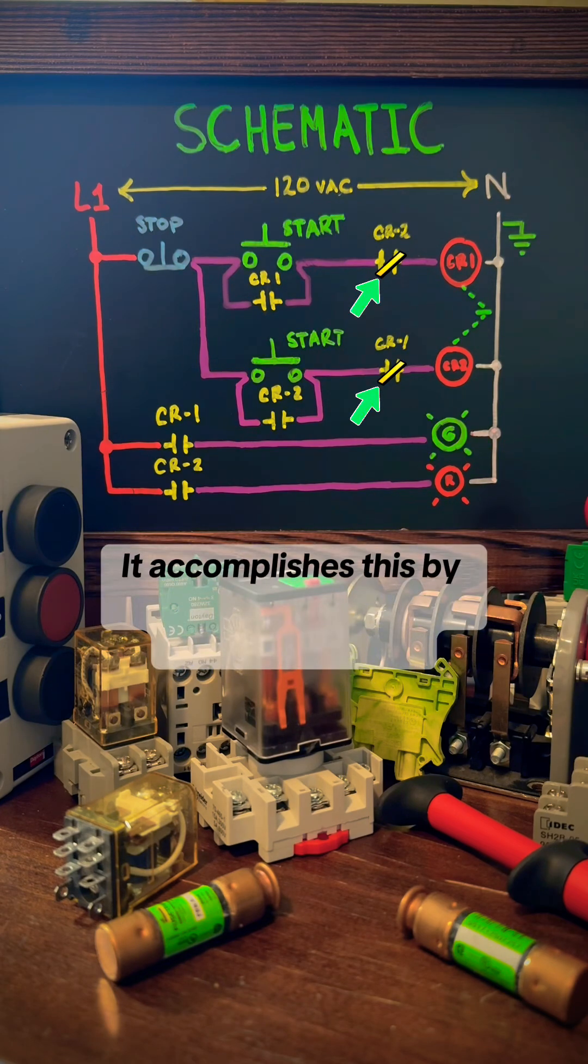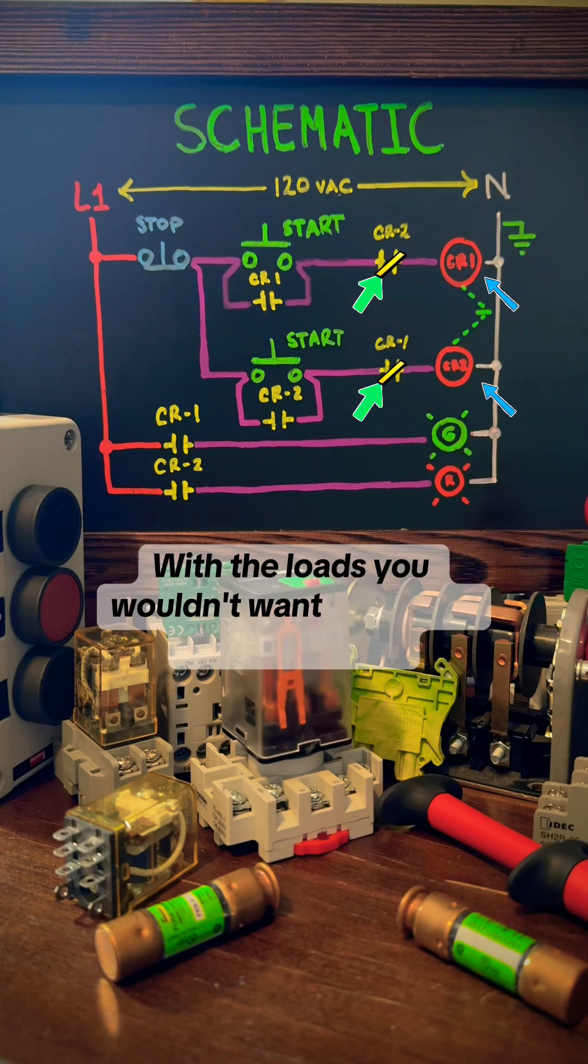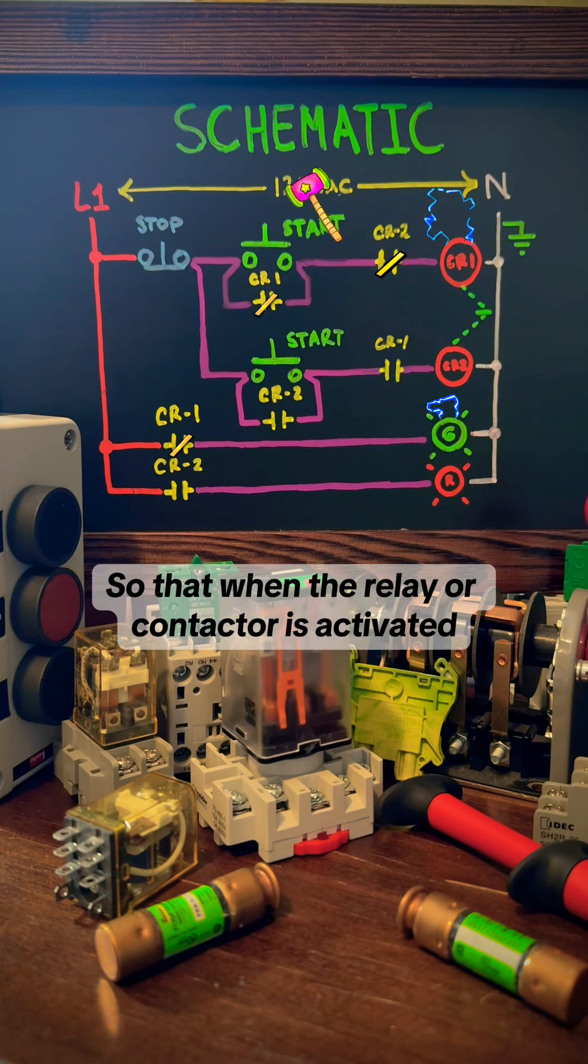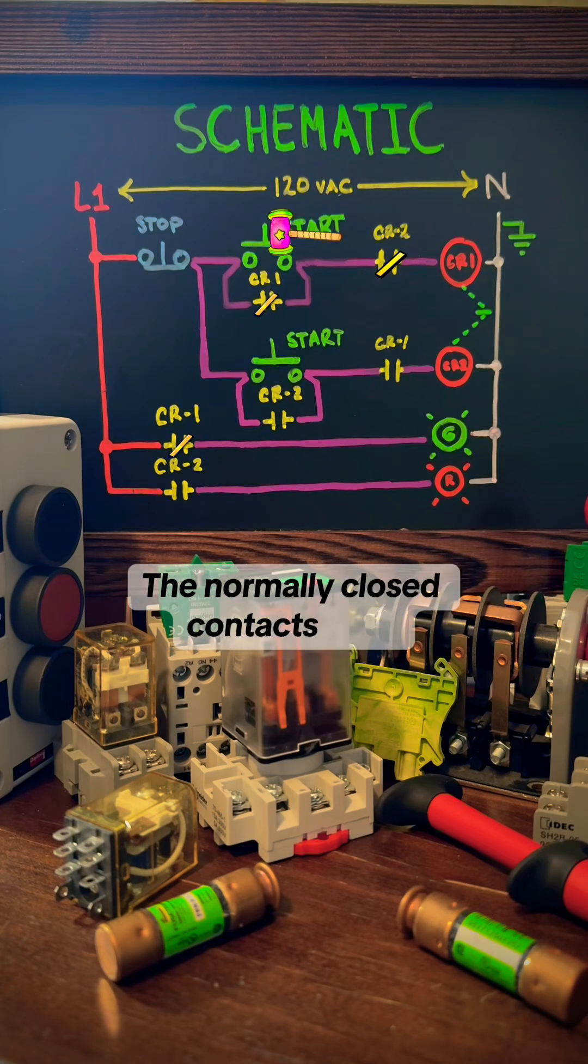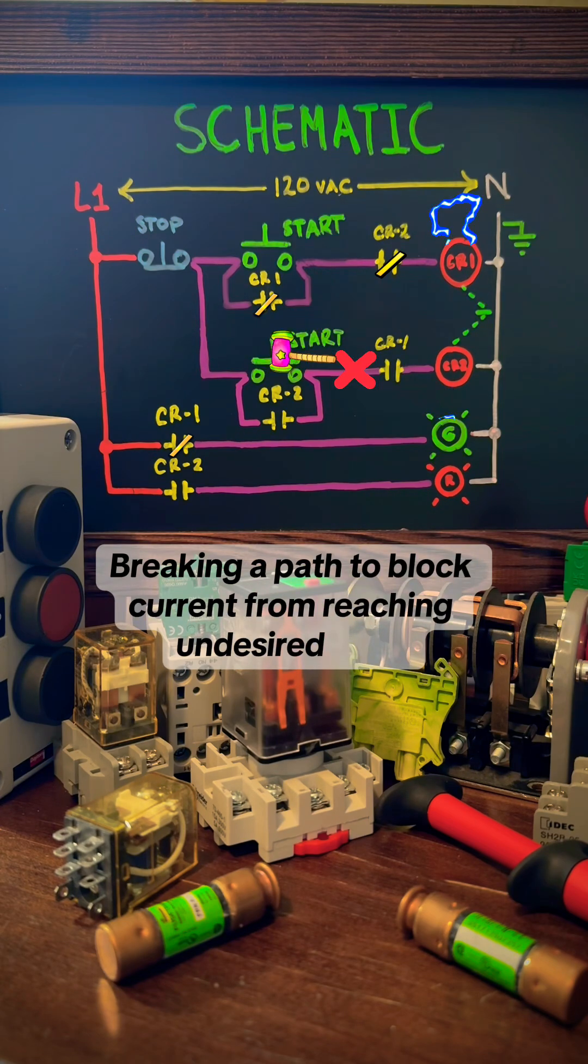It accomplishes this by placing normally closed contacts in series with the loads you wouldn't want activated simultaneously, so that when the relay or contactor is activated, the normally closed contacts open, breaking a path to block current from reaching undesired loads.